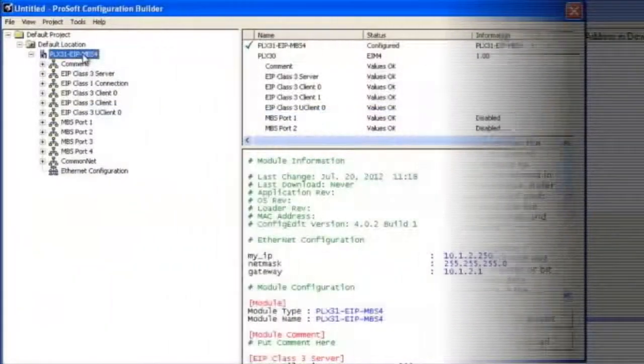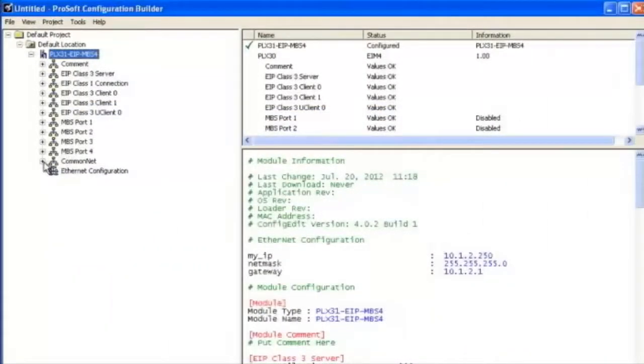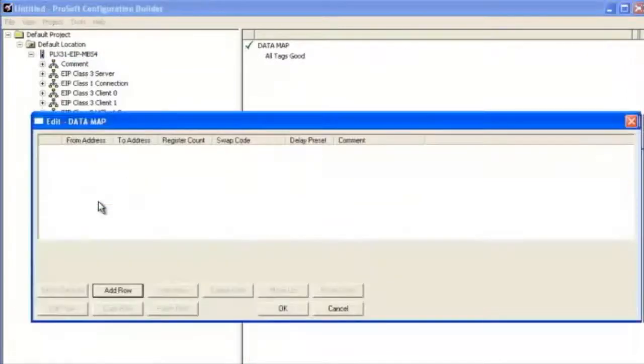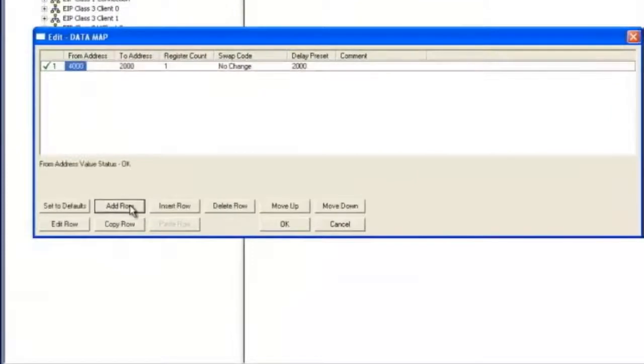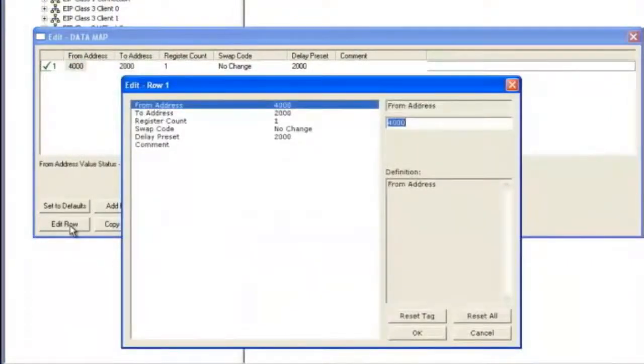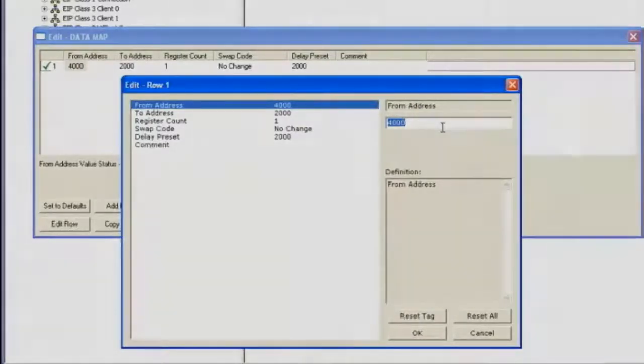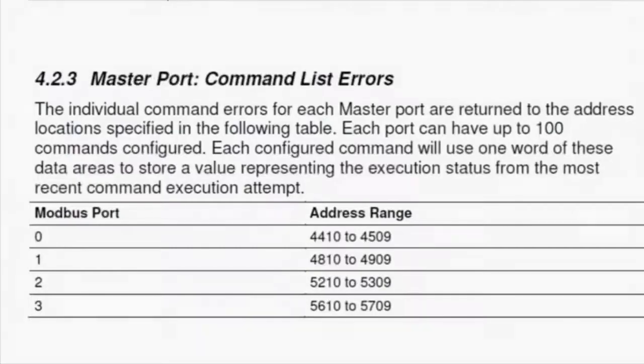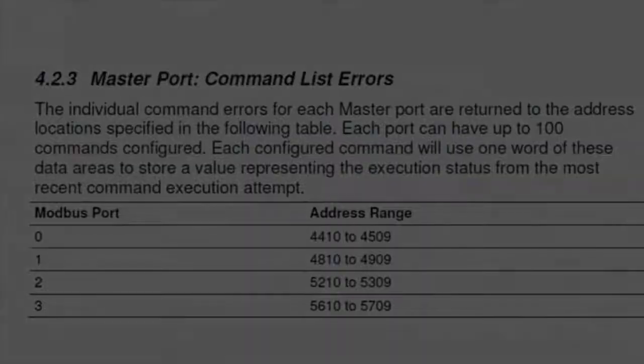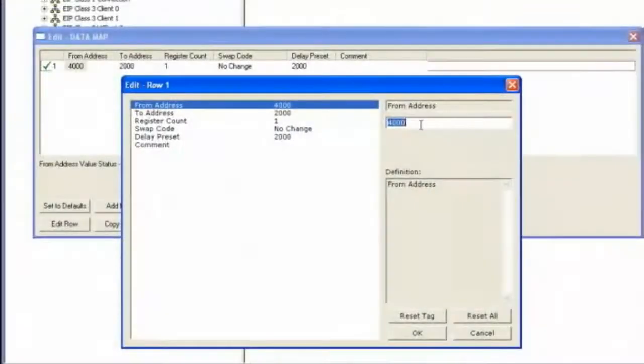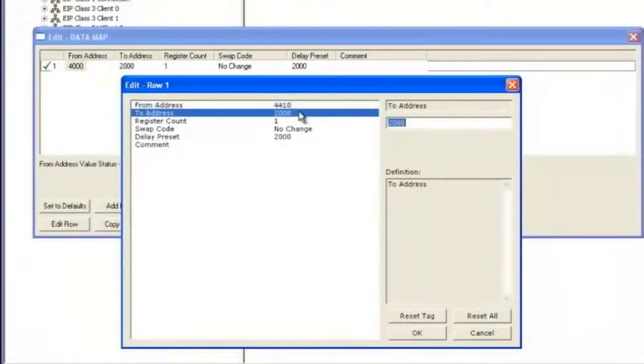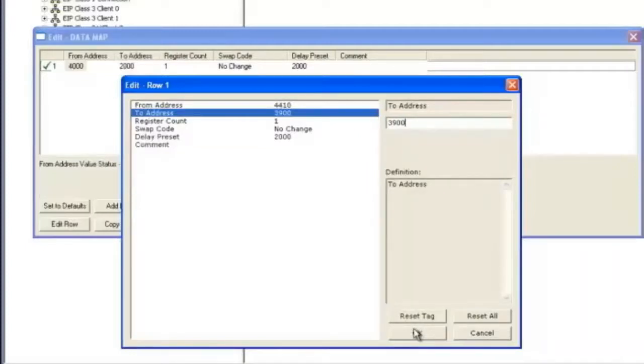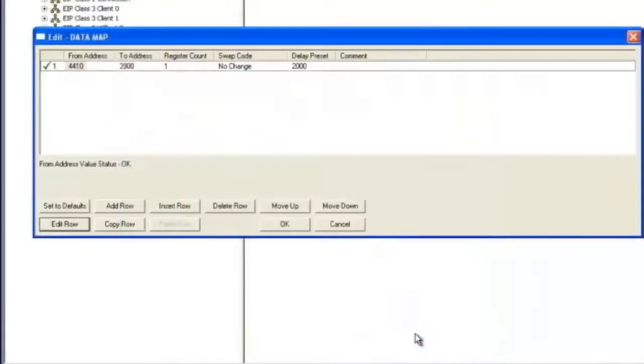Now we're going to go over using the data map. We'll select common map and go to data map. Right click and click configure. Add a row and edit that row. The data map is where you can move data back and forth in the internal database. We're going to move in status data from the Modbus master serial port. We're going to map data status data for port 1 and move that to address 3900 of our internal database. The rest is how many registers we want to move, if we need to swap to correct any data, and the interval to move that data around. This concludes the configuration overview of the PLX 31 gateway module.